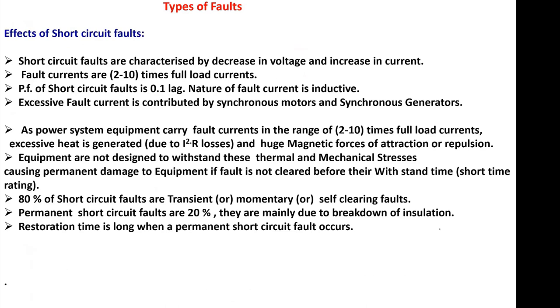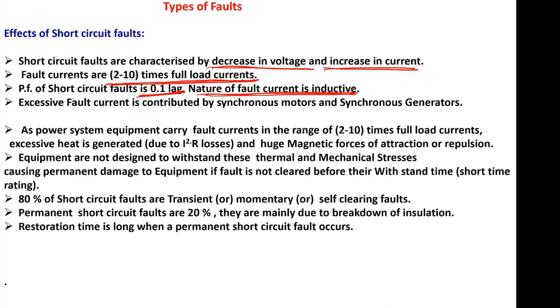What are the effects of short circuit faults? Short circuit faults are characterized by decrease in voltage and increase in current. During a short circuit, fault currents are 2 to 10 times full load currents. The power factor of a short circuit fault is ZPF lag in the ideal case (neglecting resistance), or around 0.1 lag if resistance is considered. The nature of fault current is mainly inductive.